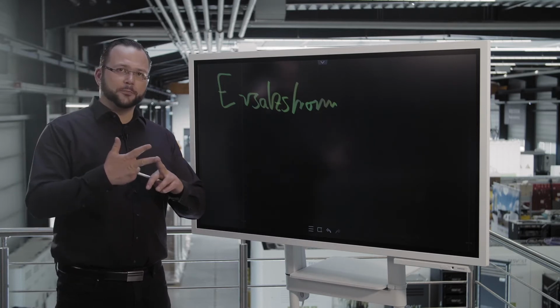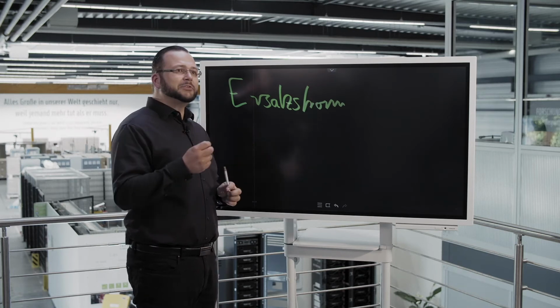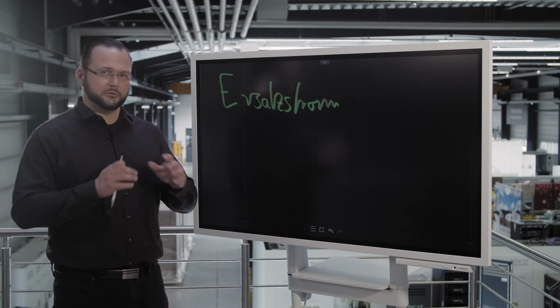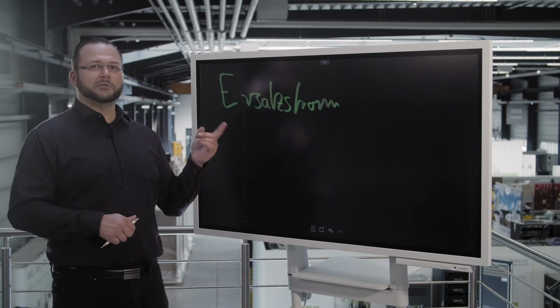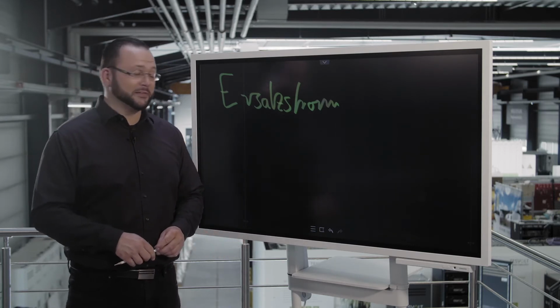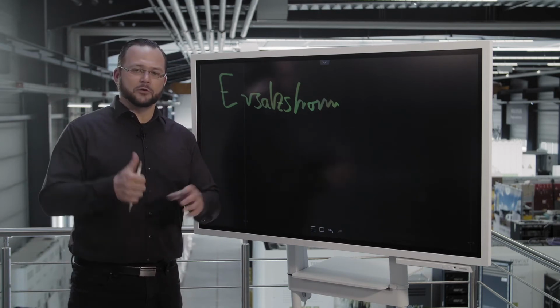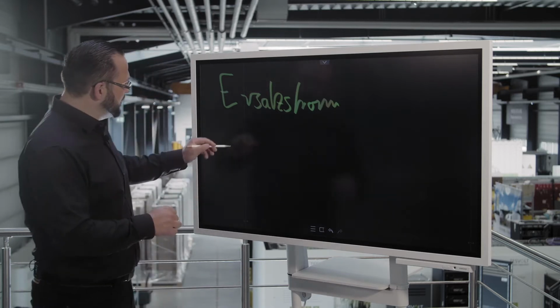We do backup power. We'll explain briefly using the topology what that involves, and then we will see why it requires over 20 milliseconds switching time. There's a lot of communication that is involved in it, and what the benefits that arise from it are, for example, operating three-phase equipment in a case where backup power is needed, which cannot be achieved with either of the other variants. So we don't do UPS, we don't do emergency power, we do backup power.